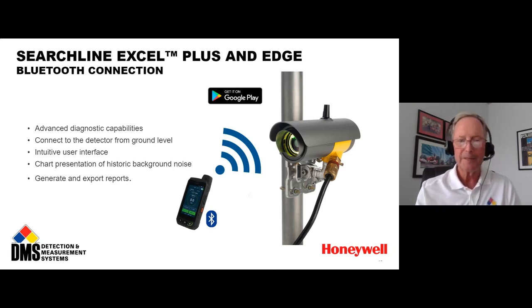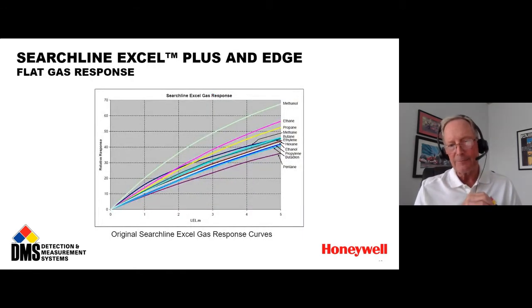The chart I just brought up here is a gas response chart of the previous Searchline Excel Open-Path Hydrocarbon Detector. At the bottom here, you'll see pentane. This is the response of that detector to pentane. We offered all of these calibrations with the previous Searchline Excel. But pentane is the gas on this list of target gases and calibrations that the previous Searchline Excel is least responsive to among the gases listed on the right.